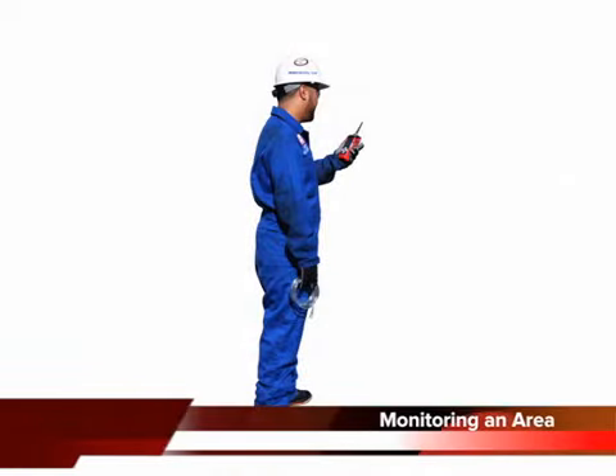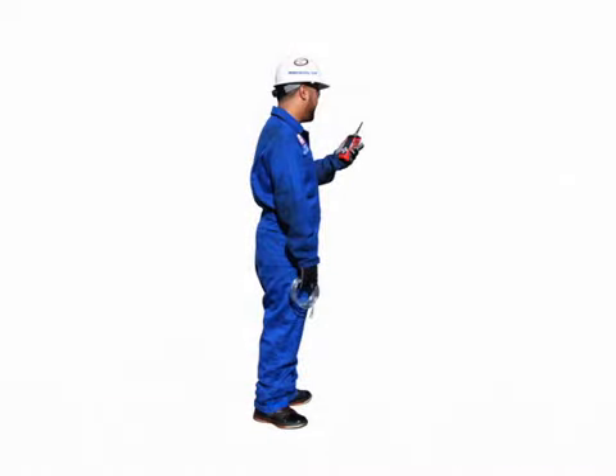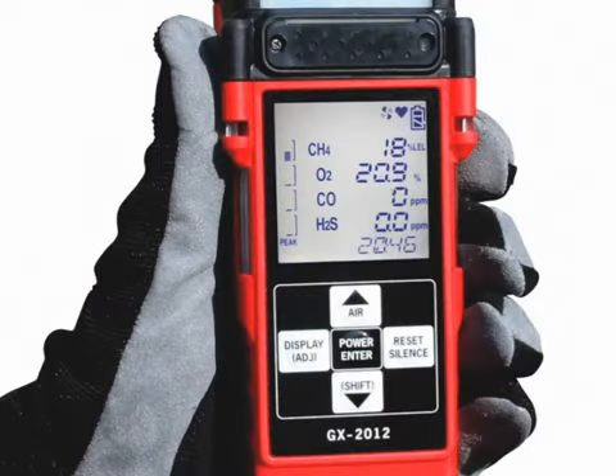Take the GX-2012 to the monitoring area. If the tapered rubber nozzle is used, put the nozzle tip in the area to be monitored. If the hose and probe is used, put the probe tip in the area to be monitored. Wait 10 to 15 seconds and observe the display for gas readings. If a reading is observed, allow the reading to stabilize to determine the gas concentrations present.